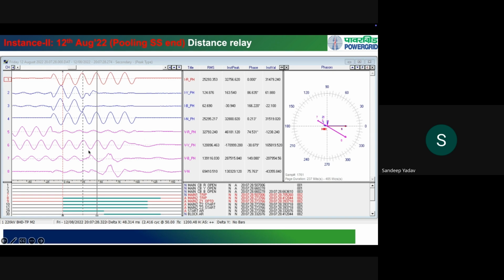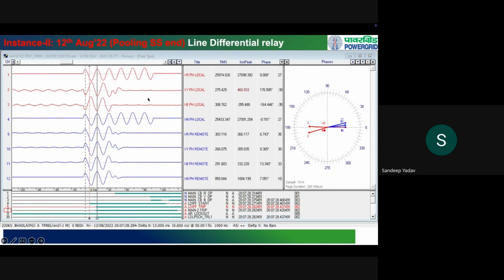Now the voltage has dropped in the faulty phase. So the voltage has come down to 32 kV and the fault current is 25 kiloampere. And this is the case of a fault current contribution from the grid side. Now let's take a look at the plant side, the solar plant side. So this is the local end, which is the grid side end. The fault current is 25 kiloampere. And this is the remote end, which is the solar plant end.